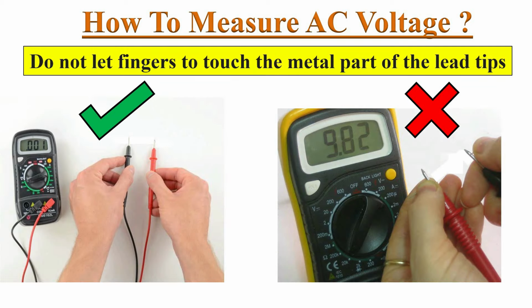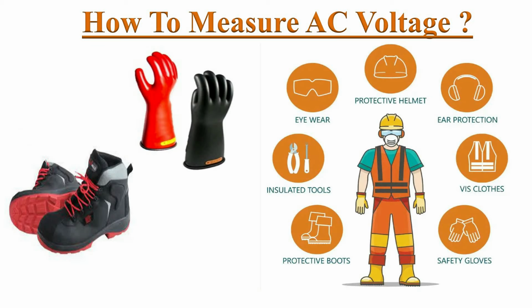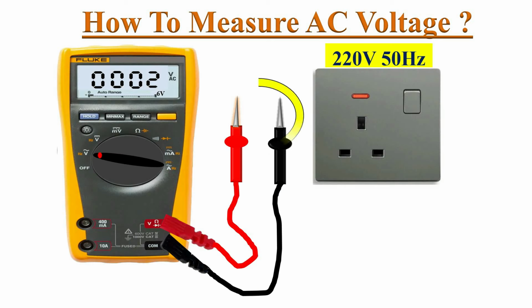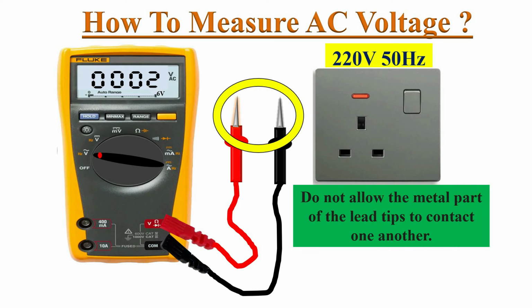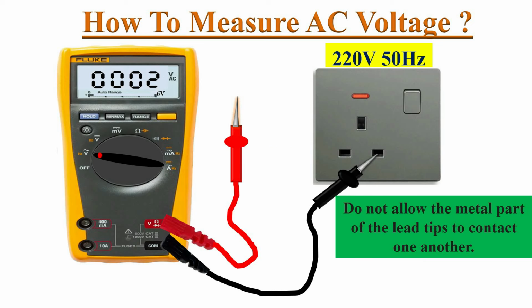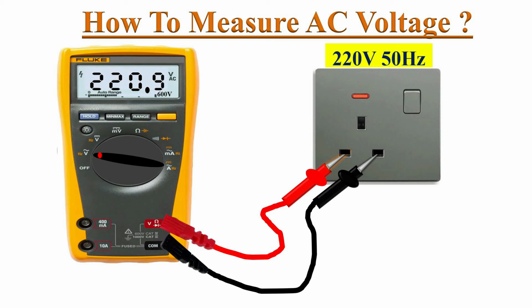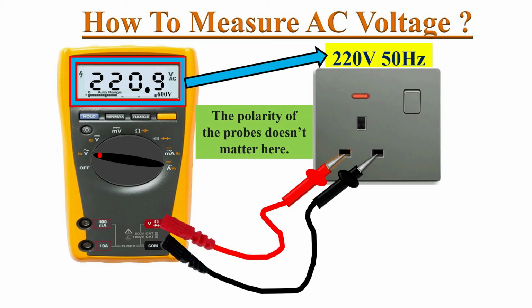While holding the test probes, never let your fingers touch the metal part of the test lead. It is highly advised to wear rubber shoes, gloves and a PPE kit. One more caution is that you should never allow the metal parts of the test leads to contact one another. Now connect the test leads to the circuit, black lead first and red lead second. We can see the AC voltage reading on the display. AC voltage does not have polarity, so the polarity of the probes doesn't matter here. This is how we check AC voltage in a circuit.